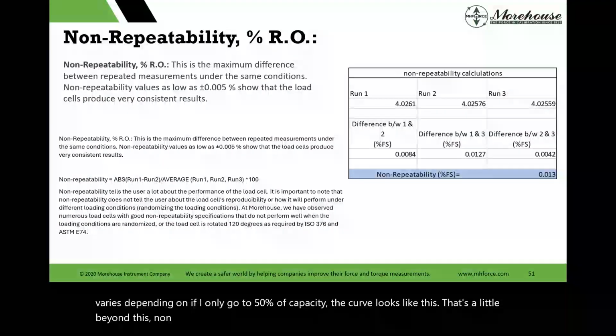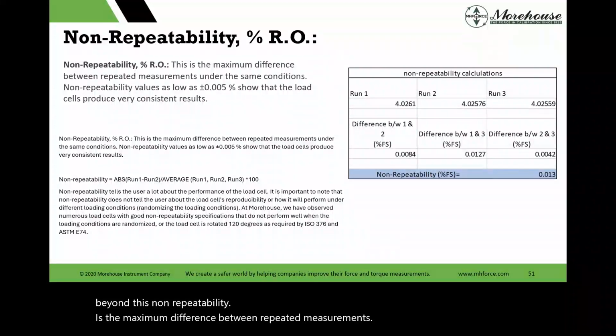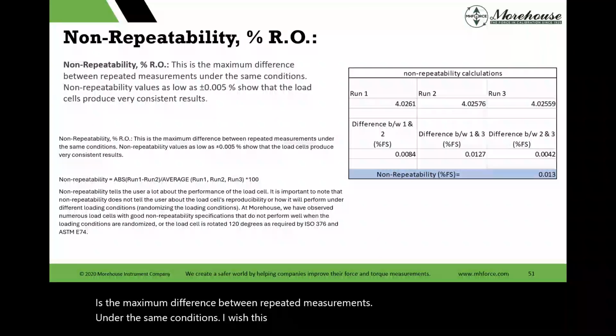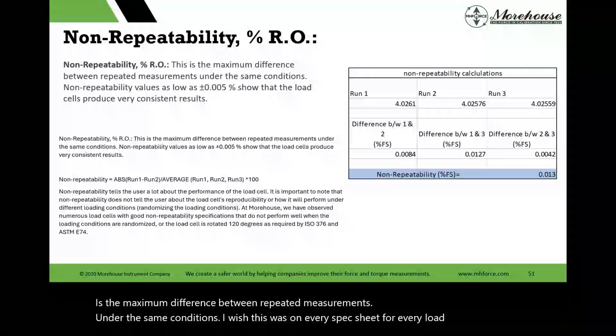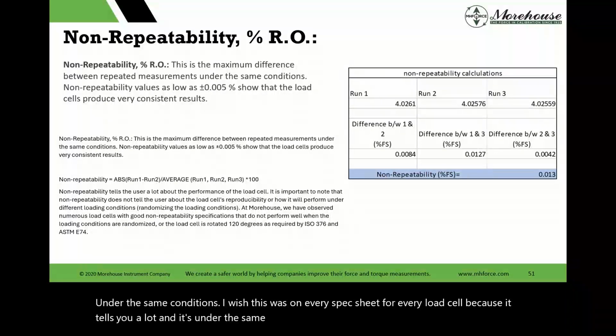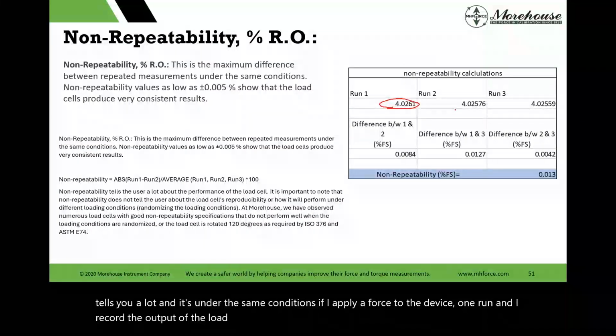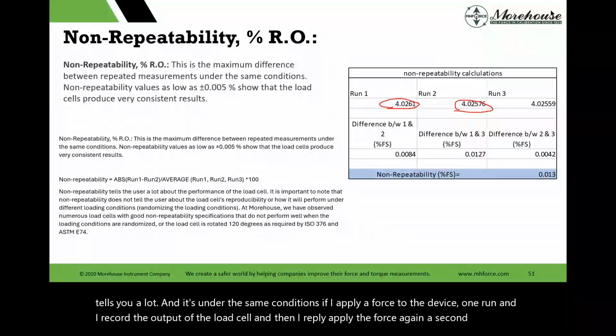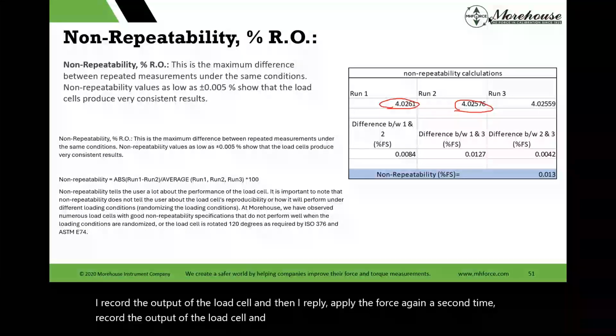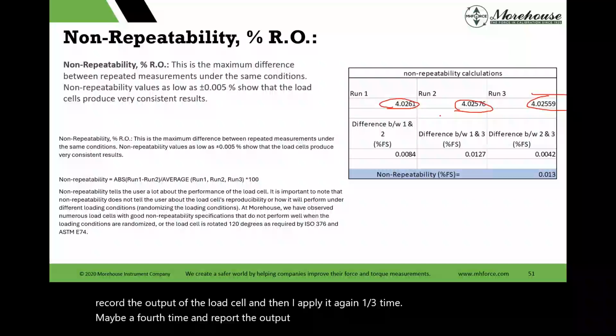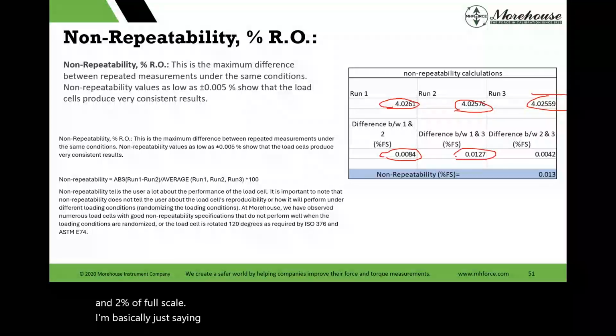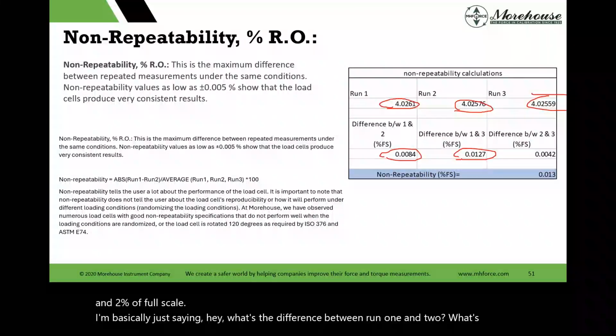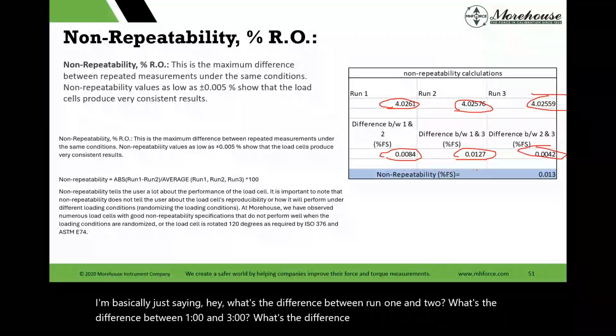Non-repeatability is the maximum difference between repeated measurements under the same conditions. I wish this was on every spec sheet for every load cell, because it tells you a lot. If I apply a force to the device in one run and record the output of the load cell, then apply the force a second time and record the output, and then a third time, maybe a fourth time, I'm basically asking: what's the difference between run 1 and 2? What's the difference between 1 and 3? What's the difference between 2 and 3?